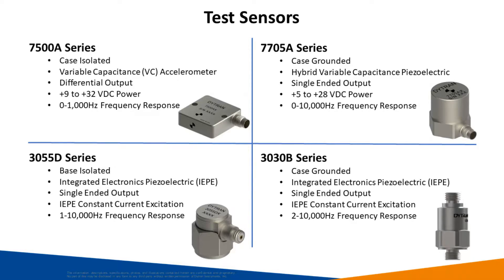The 7705 series is a case grounded hybrid variable capacitance piezoelectric accelerometer with a single-ended output. It requires a 5 volt to 28 volt DC excitation and has a frequency response of 0 to 10 kHz. The 3030 series is a case grounded integrated electronic piezoelectric accelerometer. It has a single-ended output and requires an IEPE constant current excitation. It has a frequency response of 2 Hz to 10 kHz.